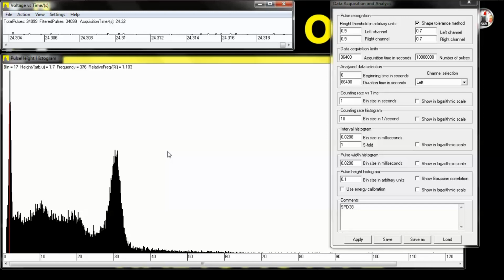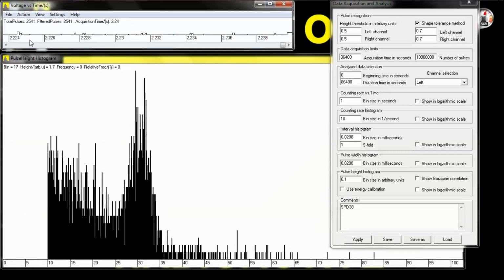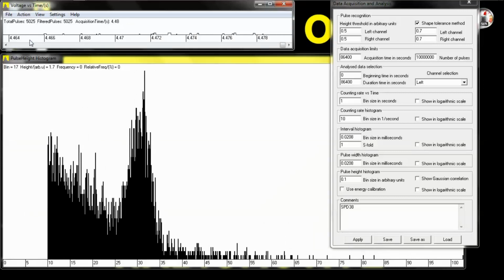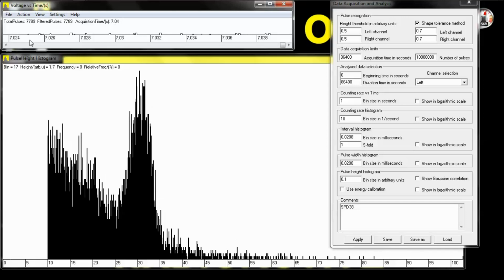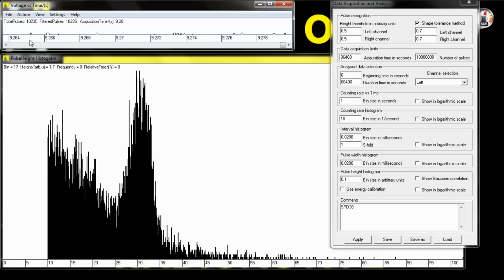But pretty much I find that 0.5 is the best setting for me. It provides the best looking spectra. Look at that. Not bad at all, though. Not bad. So let's get back to 0.5. And let's do a calibration. How to do a calibration? Well, let's get back to 0.5 again, remember. Start shape acquisition. Let's get some shape, and then we get some pulse shapes analyzed. And then we're going to save those, and we're going to do a calibration.